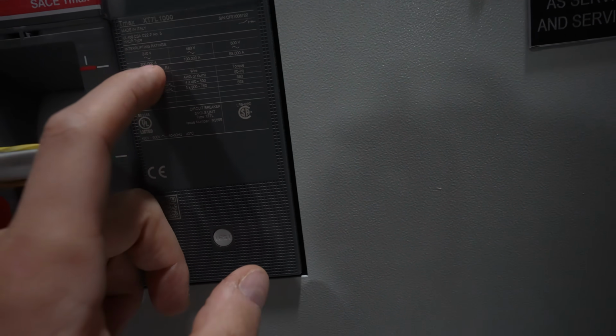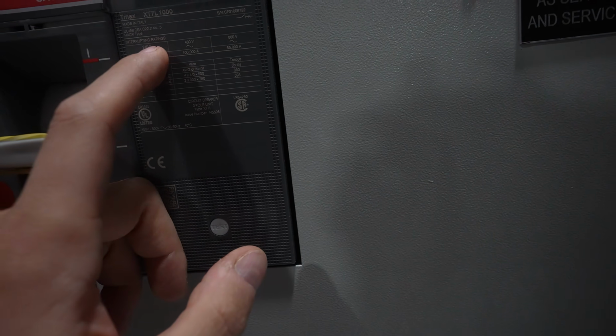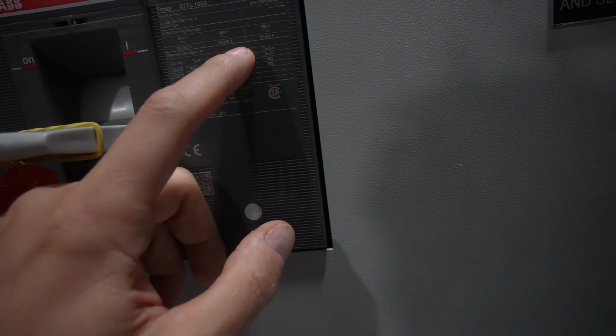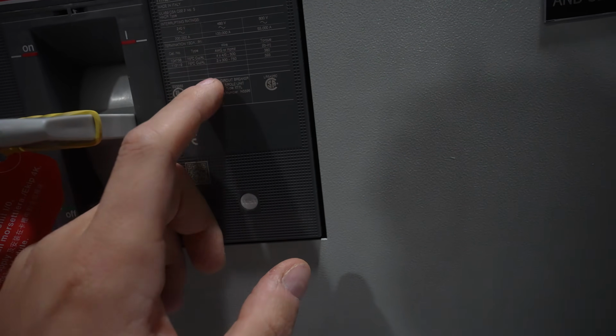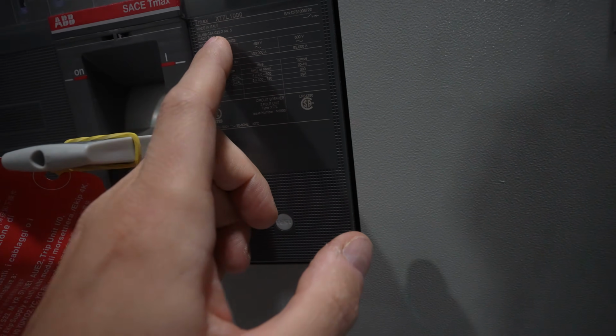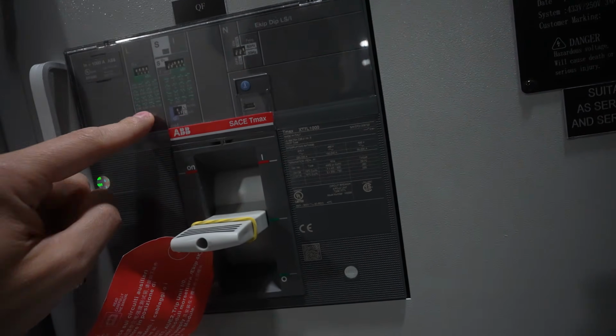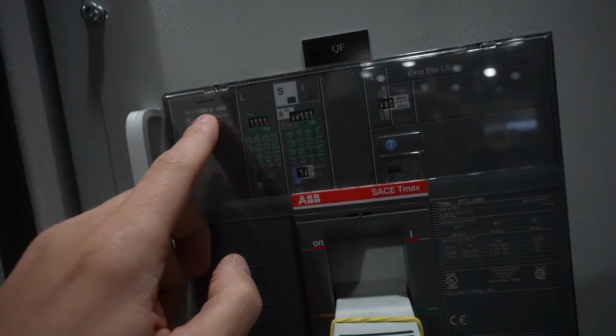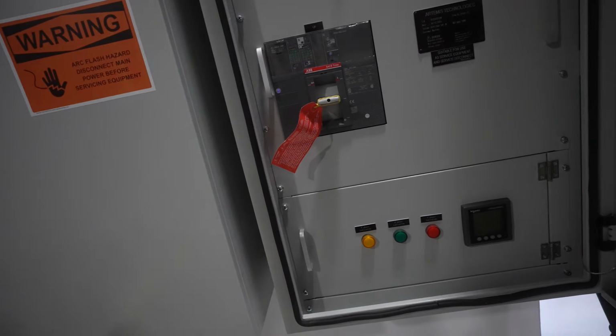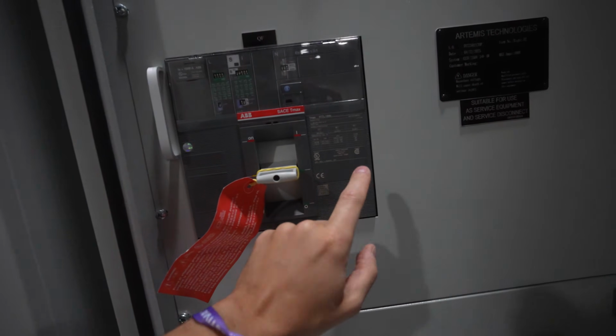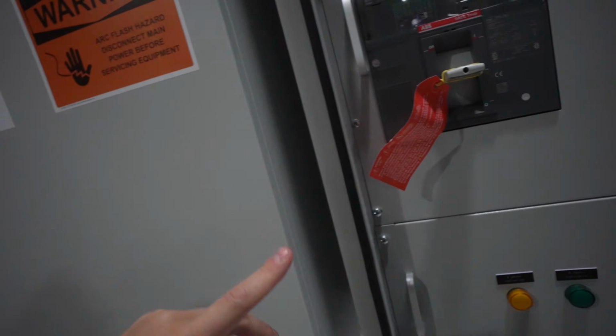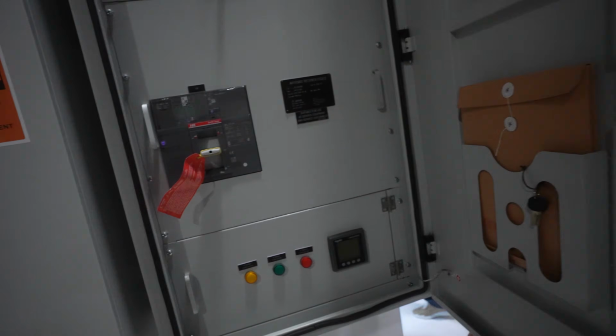Interruptible rating, 200,000 amps, I think that's the AIC rating there. That's good, made in Italy. This one here, yeah, 1,000 amp, there we go. So that's half a megawatt. And you've got 1, 2, 3, and then on the opposite side 3 more. I think 3, maybe 4. Let's go inside and take a look here.